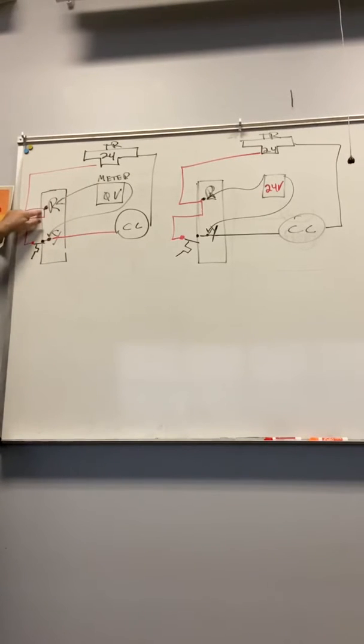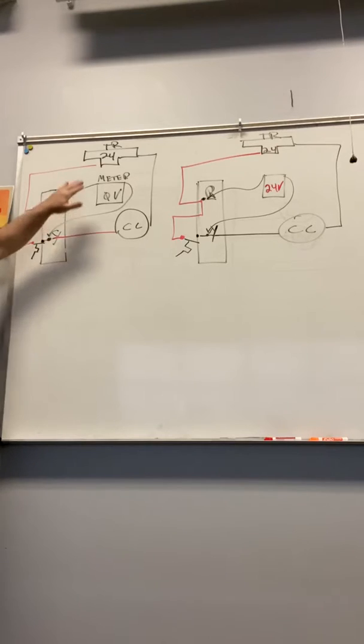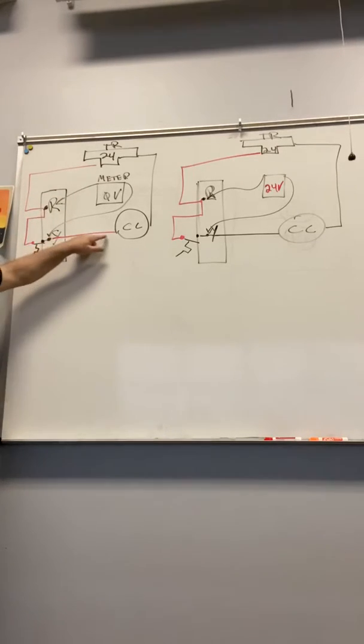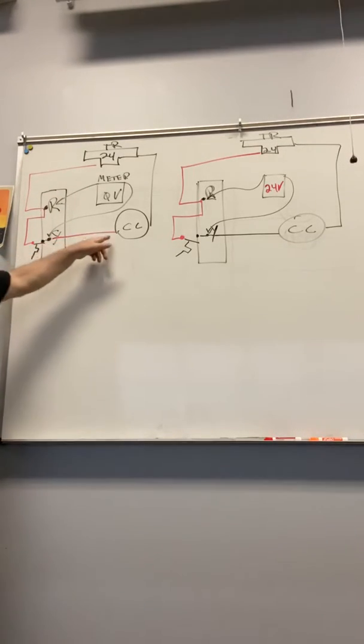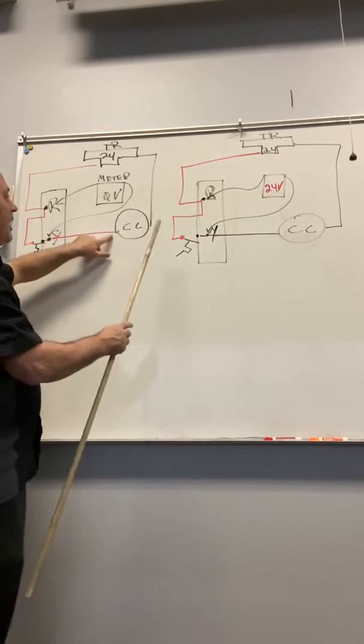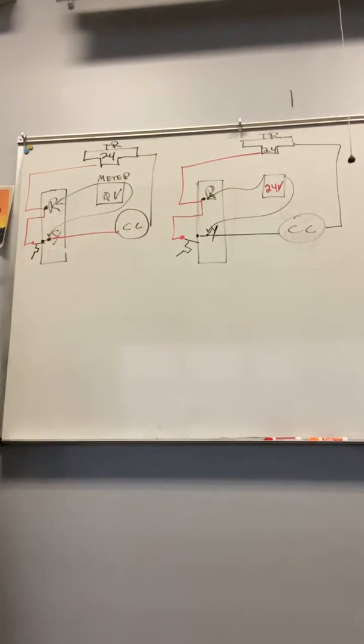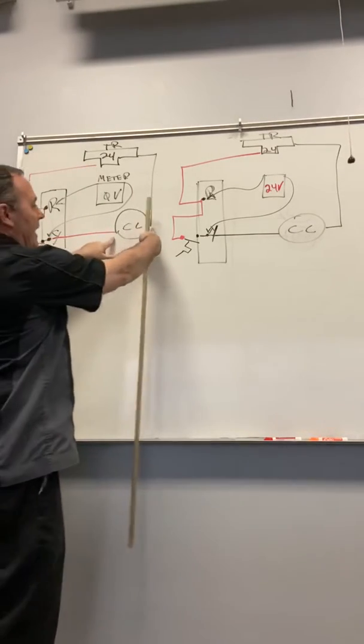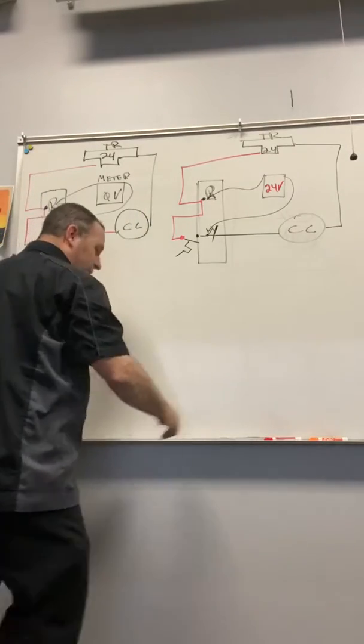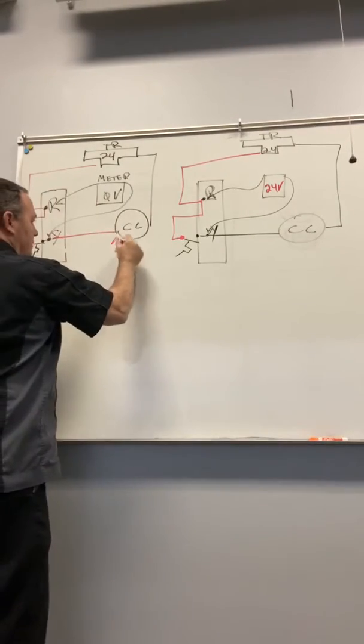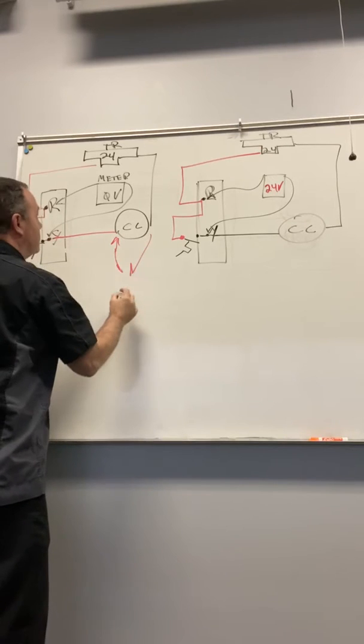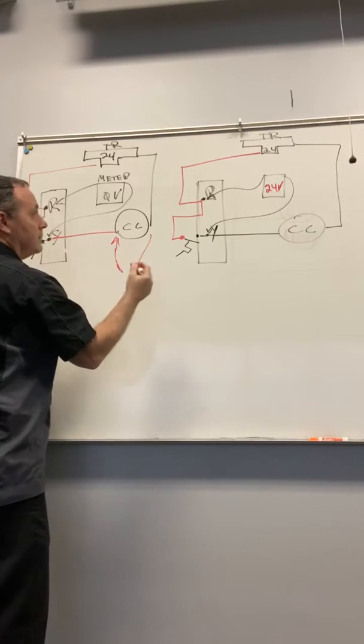So we have power going to R. R is also connected with a path to Y. Y, the thermostat's closed. Remember, whenever there's a power source and a path, it will flow. So that continues to the contactor coil. The other side of the load goes to the transformer. I'm on this side of the circuit. If I put my meter here, I would read what? What if I put my meter right here? I would read what? Anybody?